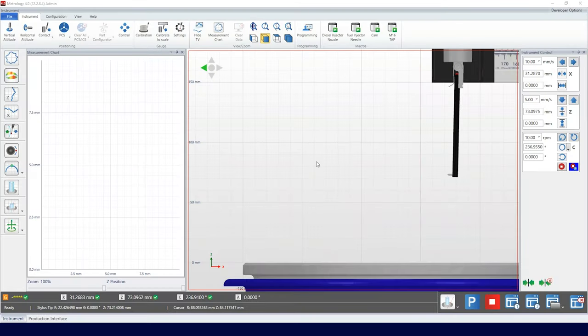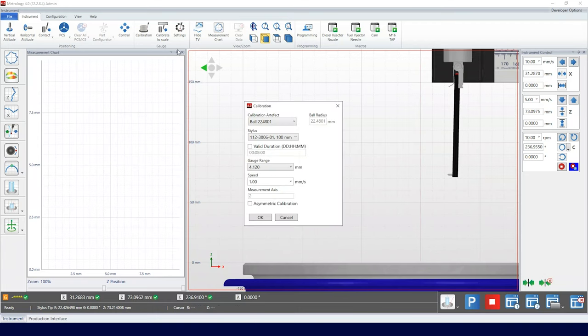To set a duration for calibration, click in the calibration menu. Select the artifact to calibrate with and the stylus. The valid duration option is ticked, and we set the time in days, hours, and minutes format.